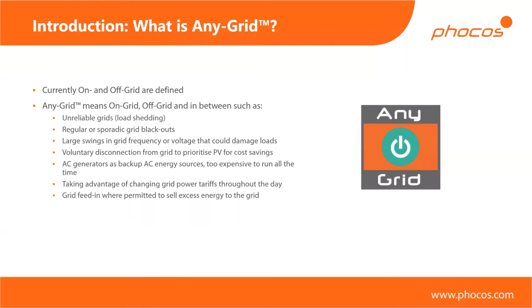So there's zero risk of injecting into the grid, for example, if you're not allowed to do so, or if you don't have a contract that you've signed with your power company. And you can still make use of that benefit of PV power to bring down your power bill. So that's what I refer to as voluntary disconnection, where the grid is existing and stable, but you're just disconnecting in order to use your own PV power.